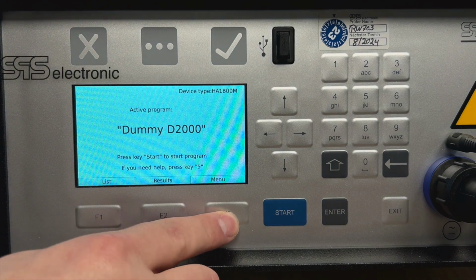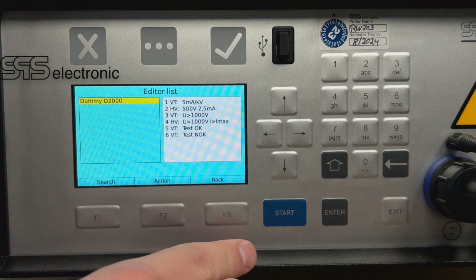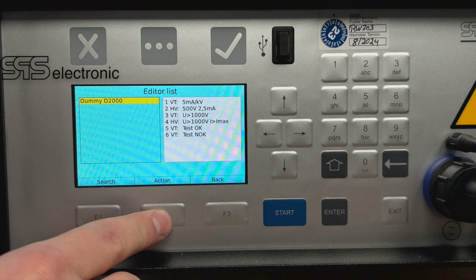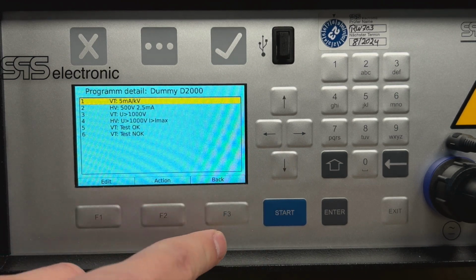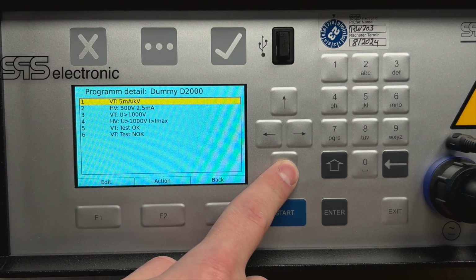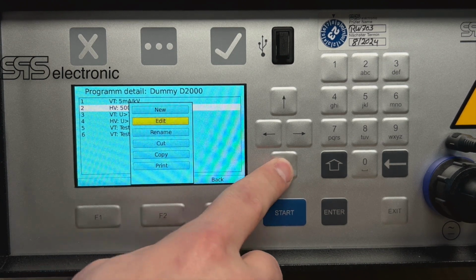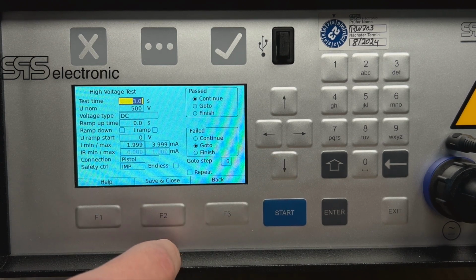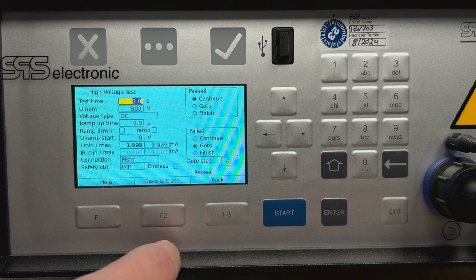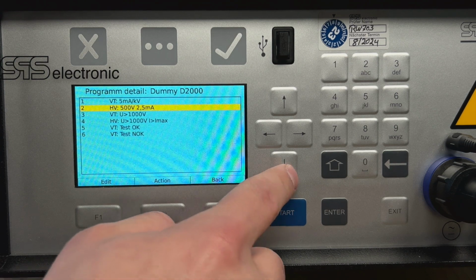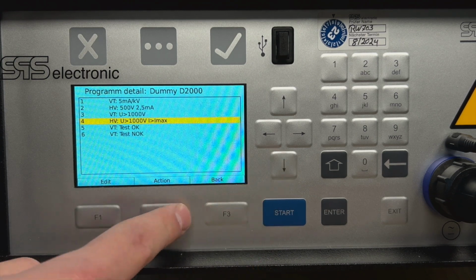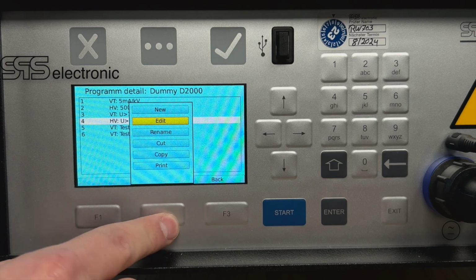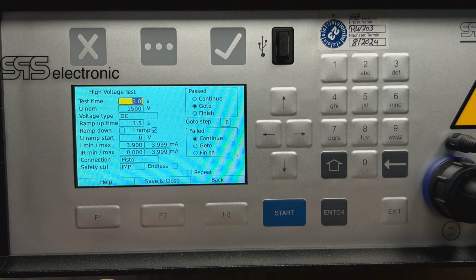For the testing, I will use our dummy test program, which contains 6 steps. 4 of them are visual steps just to inform us, and 2 of them are actual measuring. The first one is a visual step to inform us what to do. The next one is high voltage, where I will set up 500 volt DC, and as a result I should get 2.5 mA. The next one is also a visual step to inform us what to do, and the next one is a high voltage test for short circuit. I will set up 1.5 kV DC, and at 1 kV the test should fail because of the short circuit.